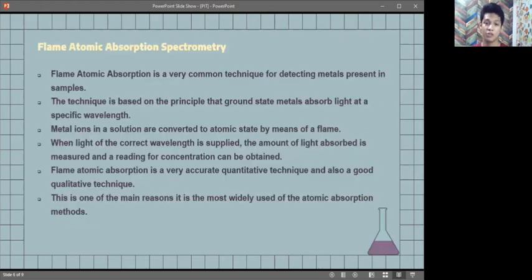Flame Atomic Absorption is a very common technique for detecting metals present in samples. The technique is based on the principle that ground state metals absorb light at a specific wavelength. When light of the correct wavelength is applied, the amount of light absorbed is measured and a reading of concentration can be obtained. Metal ions in a solution are converted to an atomic state by means of flames.